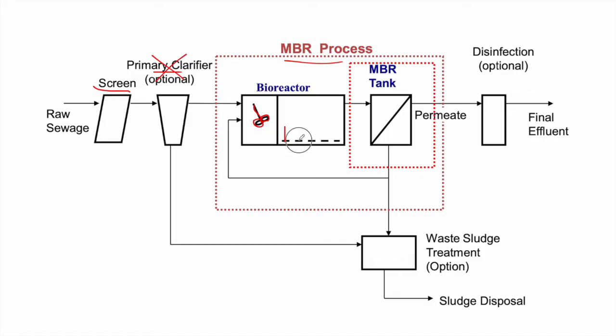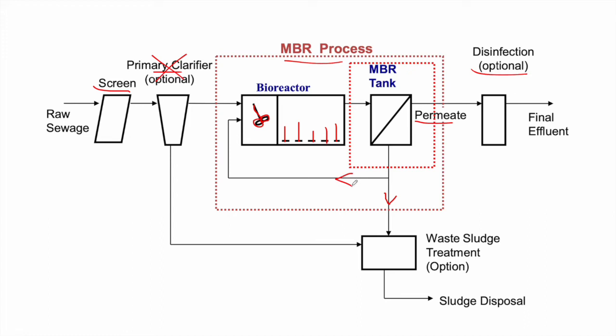Then we have the aerobic stage with injection of air. In the anoxic stage, we have denitrification; in the aerobic stage, we have nitrification. In these stages, we achieve very high reduction of nitrogen, phosphorus, COD, and BOD. Then the water goes through the MBR tank — the membrane filtration. The permeate or clean water will go through disinfection if required, or can be safely disposed of or reused. Activated sludge is formed — some is disposed of as wasted activated sludge, undergoing further treatment, and the other part is returned as returned activated sludge.